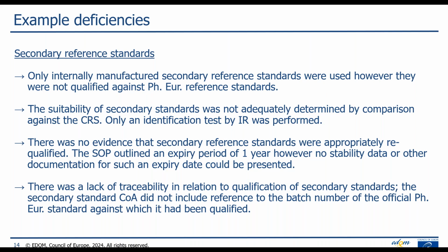And then the last example, there was a lack of traceability in relation to the qualification of secondary standards. So the secondary standard COA did not include reference to the batch number of the official European Pharmacopoeia primary standard against which it had been qualified.